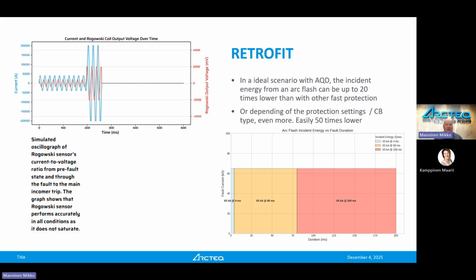Rogowski is also frequency dependent. So 50 Hertz and 60 Hertz have a slight difference. If we are at 100 millivolts with 50 Hertz, we are at 120 millivolts with 60 Hertz. And don't worry, you can use the same equipment in 60 Hertz countries and 50 Hertz countries without any hesitation. And then there's a drawing here on the right side.